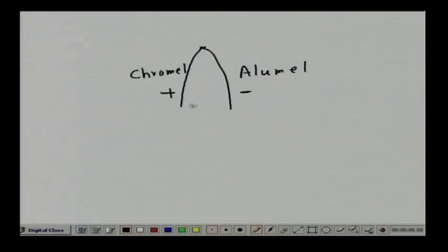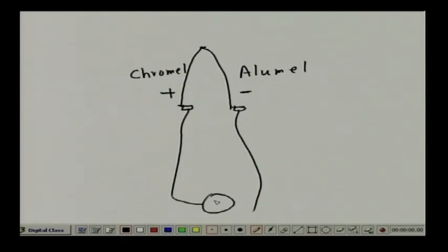Now, the problem is that if you have a platinum, platinum-rhodium type thermocouple, you cannot use platinum, platinum-rhodium lead wires, because it will increase the cost of the entire system. The thermocouple is available like this, with a terminal here. So you connect the lead wires there, and it will come to your voltmeter. So you will get a voltmeter. Is that not so?